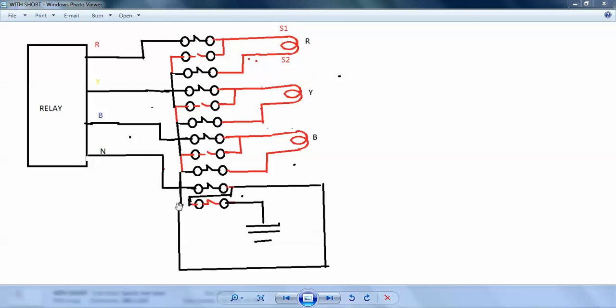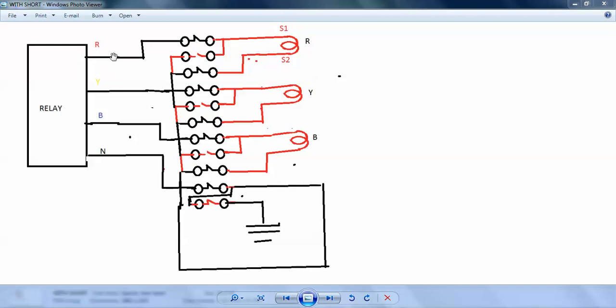These links are here provided to facilitate shorting CT in live case. If you are going to take any maintenance in this relay, you don't want to shut down the feeders. Just short the links, then you can take maintenance of the relay or test the relays or change the setting, whatever is your requirement. You can use these shorting links to short the CTs.